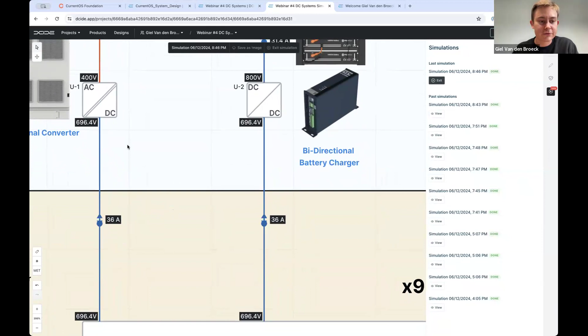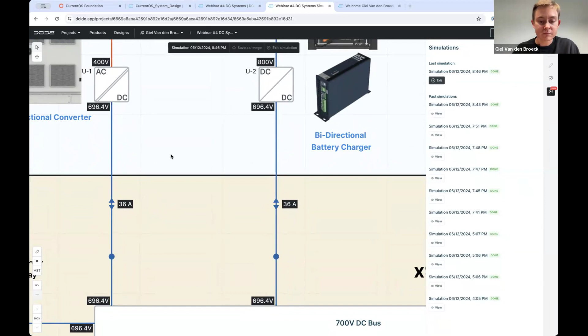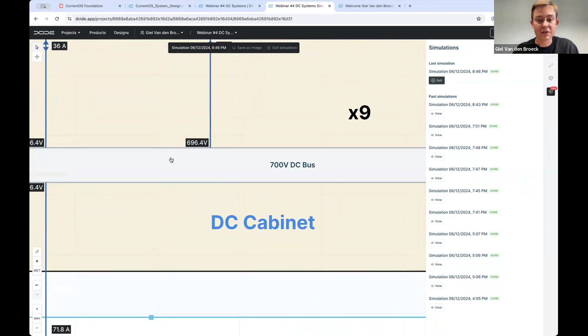So you see now that the total output current of 72 amps is now provided by the two sources in your system. So the battery and your grid side interface converter, each contributing 50% of the total load current because their Droop resistances are equal in this case. And the rest of the system remains in the same state as we had before.